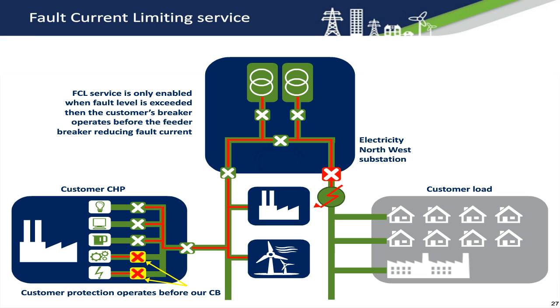In this example, the red circuit breaker fault level has been exceeded, so the fault level assessment tool could enable any of the circuit breakers in yellow at the customer's premises to operate. They will operate quicker than the red circuit breaker, reducing the fault level in the network, so the red circuit breaker can operate safely beneath its fault rating.